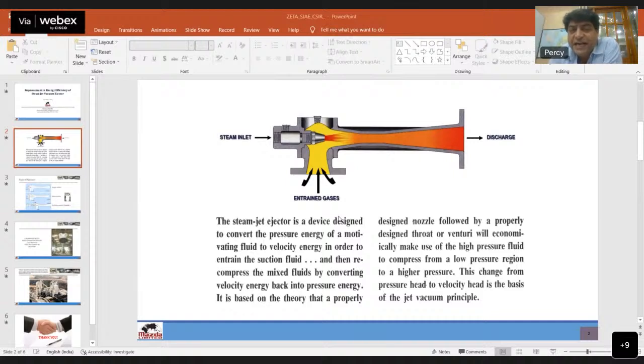So this is a simple ejector. How it works: high pressure steam passes through the nozzle of the ejector. It creates very high velocity steam, and because of that high velocity steam which comes out of the nozzle of the ejector, all the surrounding process vapors get entrained or sucked by the ejector, and you have vacuum in the distillation column or in the evaporator or in the reactor.